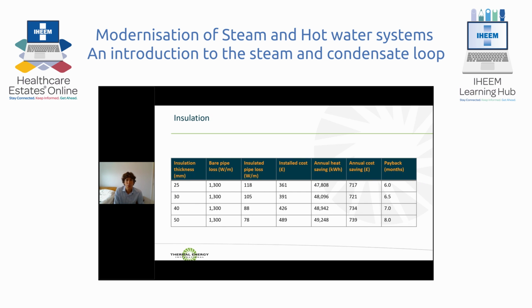Insulation within the distribution system has one of the fastest returns on investment. Damaged insulation can allow water ingress and actually increase the heat losses because you're then actually evaporating water off the pipe. In extreme circumstances, you may even notice that your gas consumption increases on wet days. If you see this within your facility, this is a good indicator that you've got serious water ingress within your system.